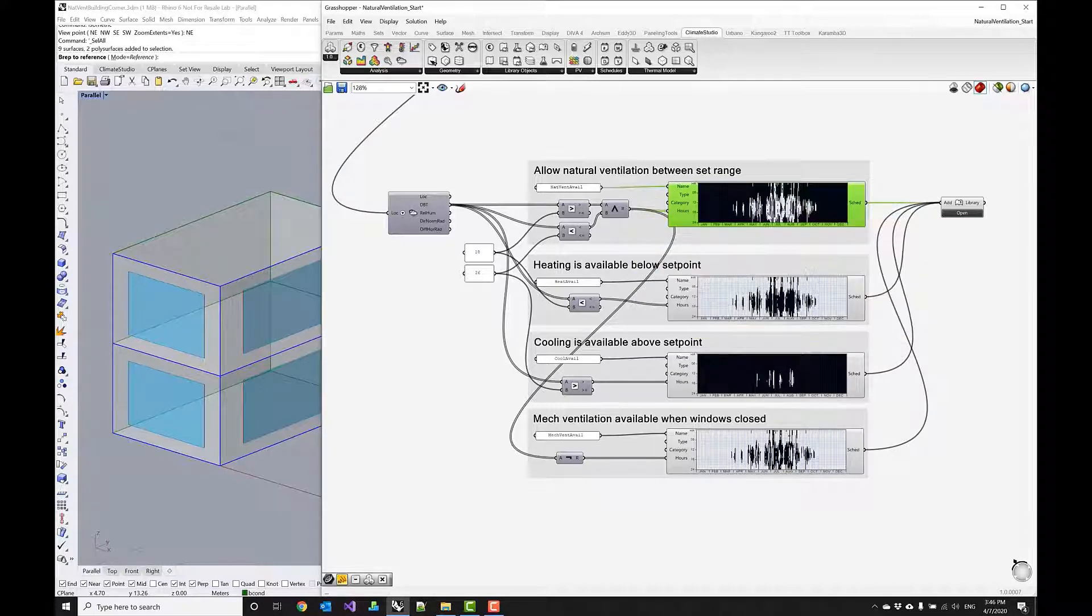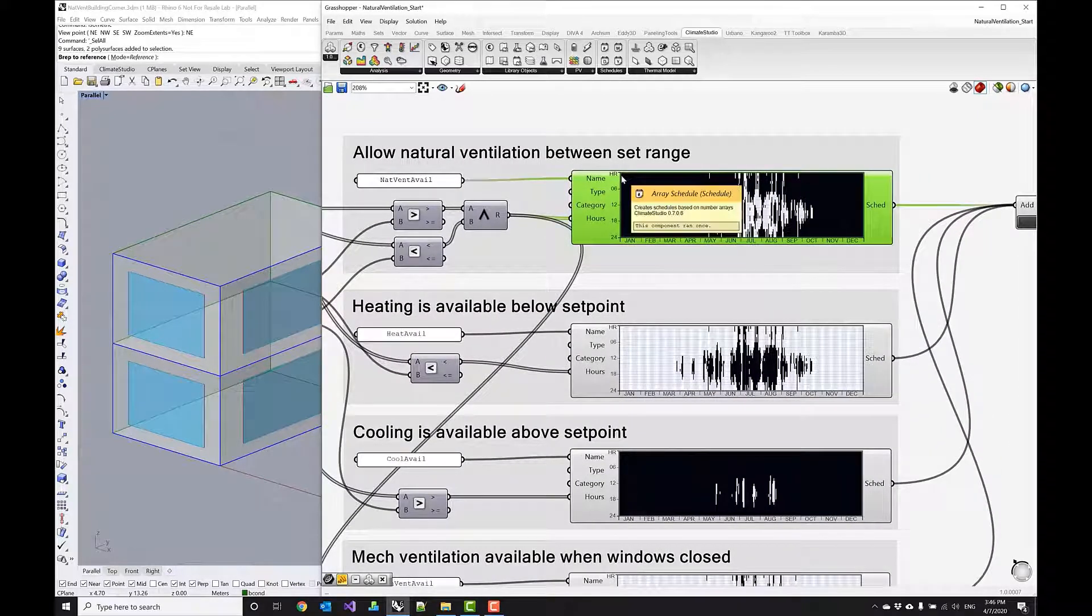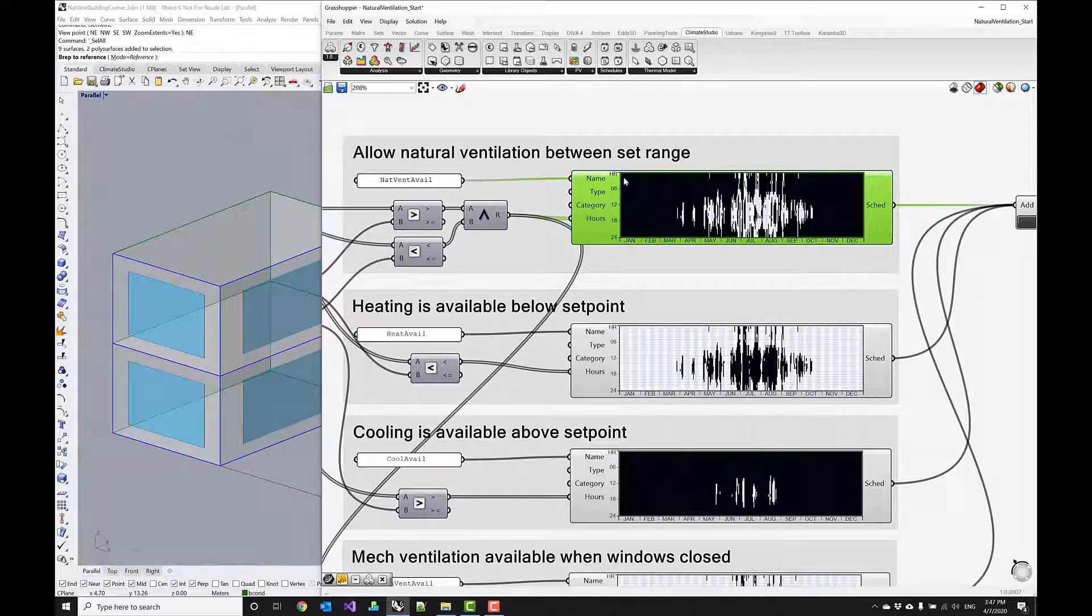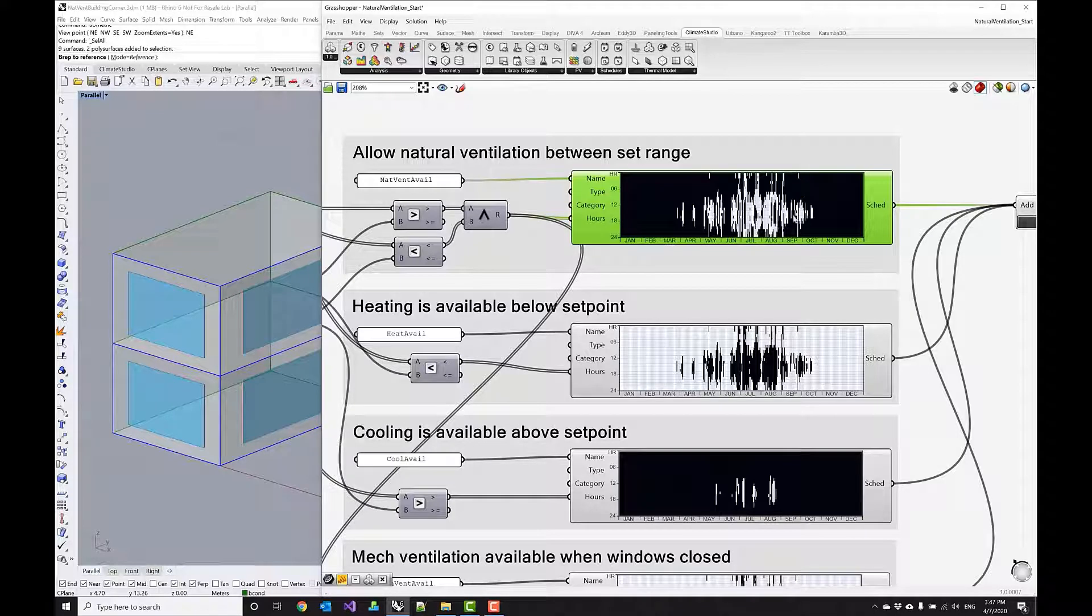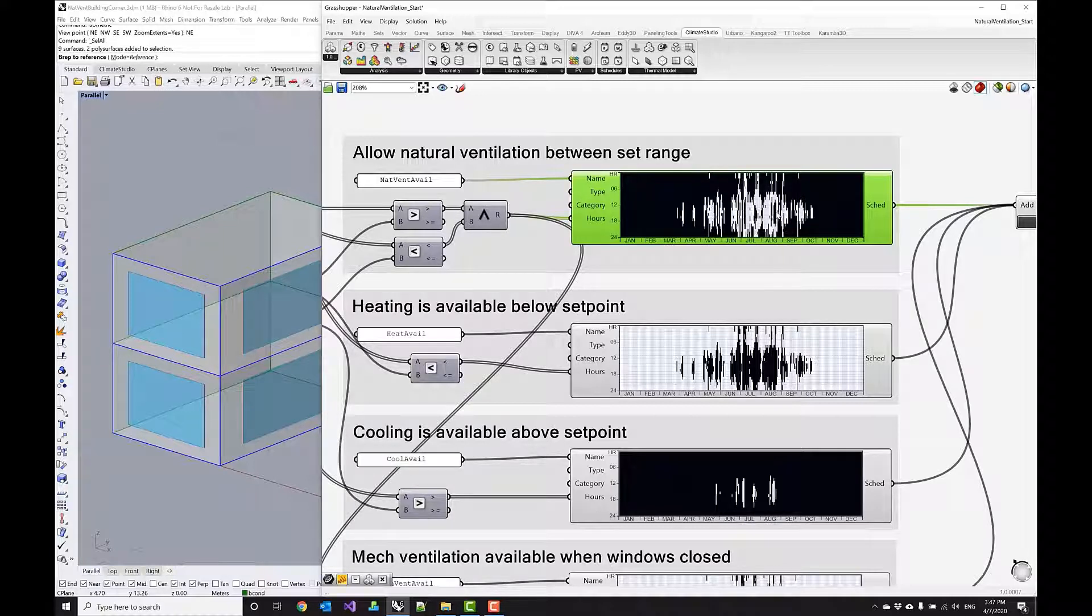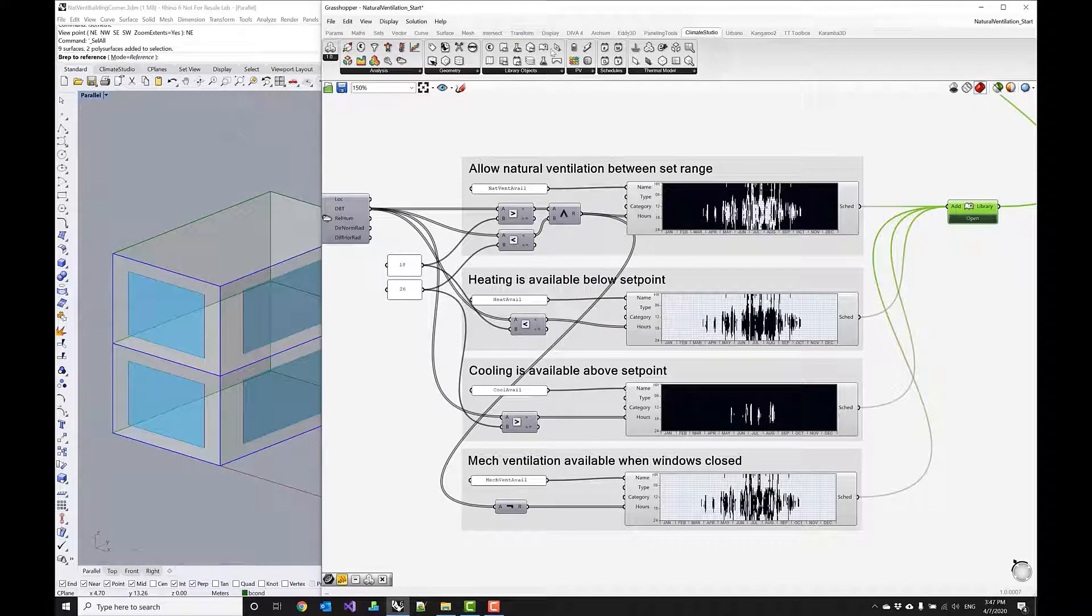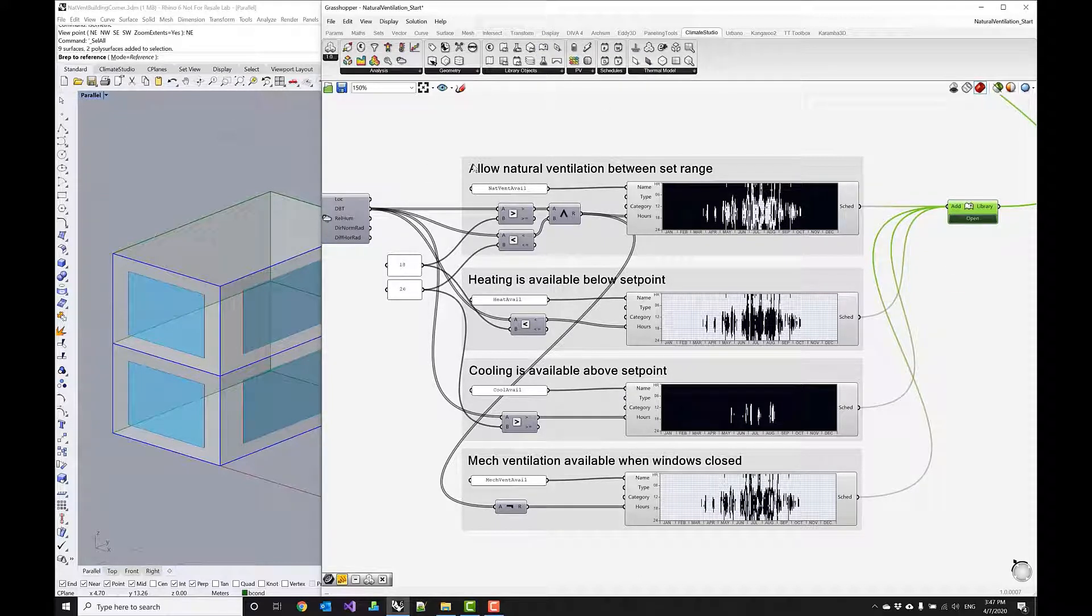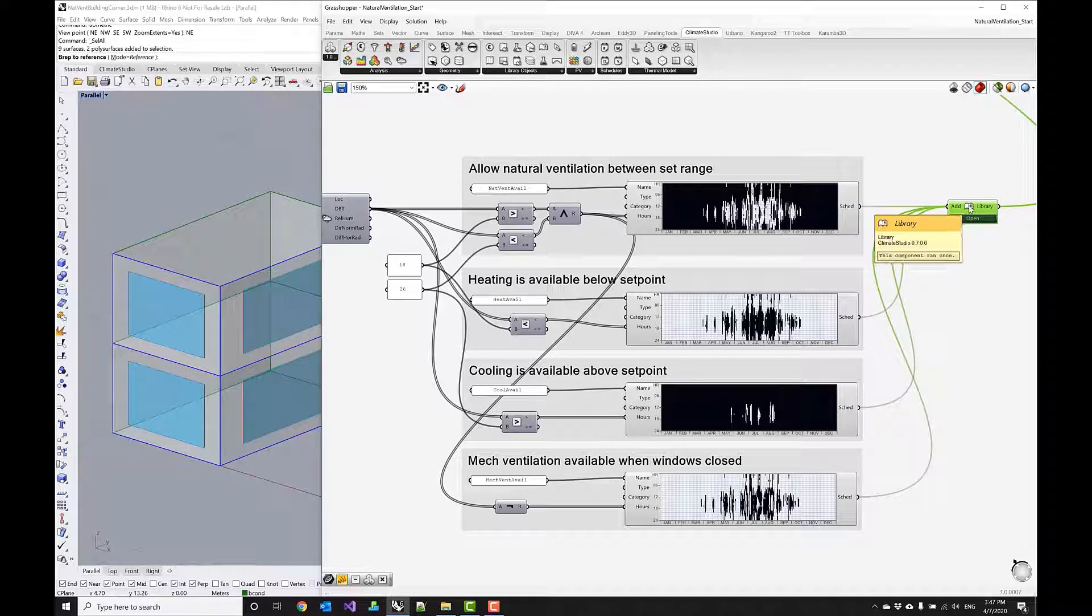and then I'm providing basically all the hour values and you see these are automatically converting from true false to zeros and ones and then you can see here nicely plotted in this heat map where you see the hours on the y-axis and basically every day plotted on the x-axis and you see when natural ventilation throughout the year would be available in this case right so only in the summer months and then even here in the evenings it becomes too cold turns off and then there's a couple of spots in the middle where it actually is too hot for natural ventilation and then lastly I'm passing the schedule into a library component which you can find up here and this basically adds the schedule that I just created parametrically within grasshopper to the library within this grasshopper file.